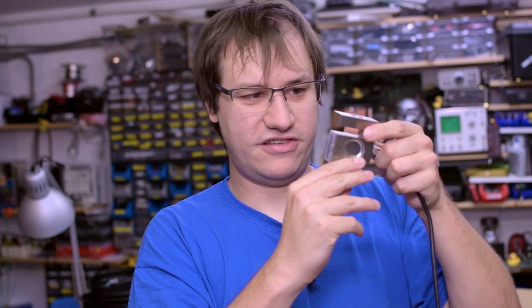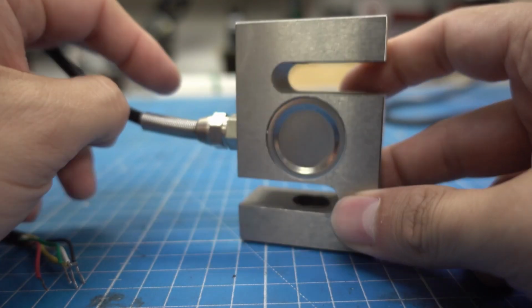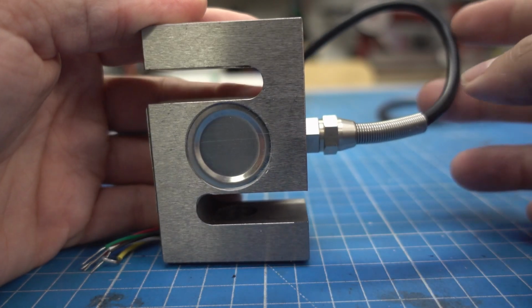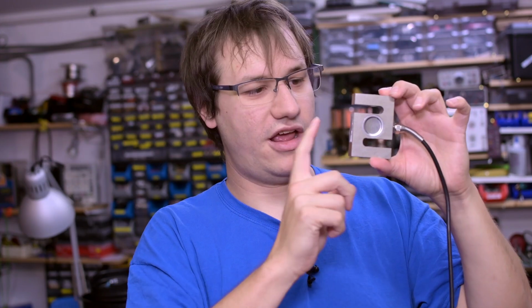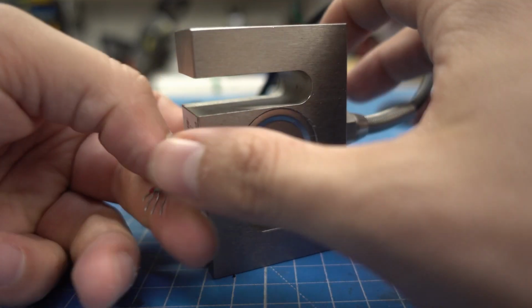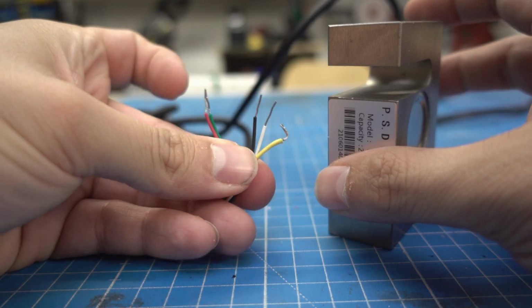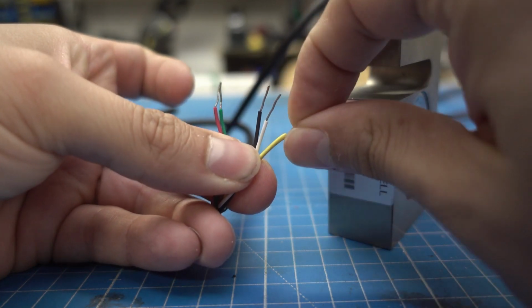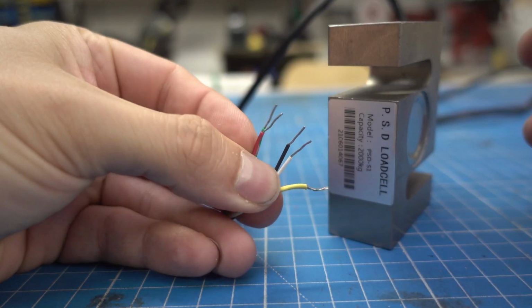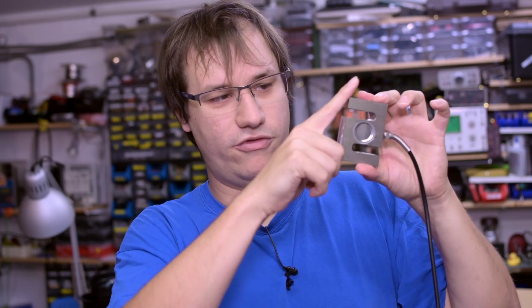You mount it not like that, you mount it like this. So the part that is actually moving is inside here in this circular thing. There are 4 strain gauges in there forming a Wheatstone bridge, aka a load cell, and then you have a cable to put that out. You basically get 4 cables on there, or 5 on this one. We have inputs plus and minus, then you have outputs plus and minus, and a ground wire for the case.